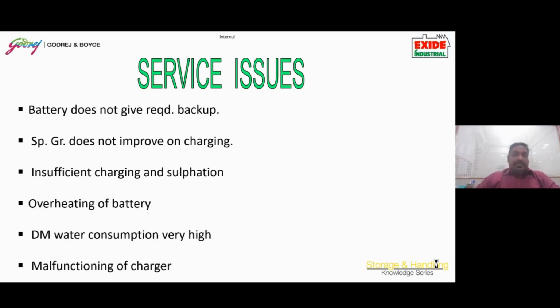If overheating is happening, there could be two main causes. One is the external environmental operating condition—if it's extremely hot, overheating of the battery might happen, and there's no way other than providing some cooling or respite to the battery. Another possibility is some minor short inside the cell causing the battery to overheat. If overheating happens, the OEM must be informed and the person will come and diagnose it. If a short is detected, we shall replace the affected cell, charge the battery again, and put it back into operation.